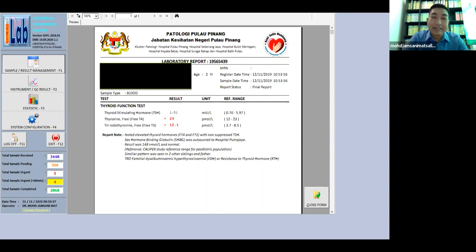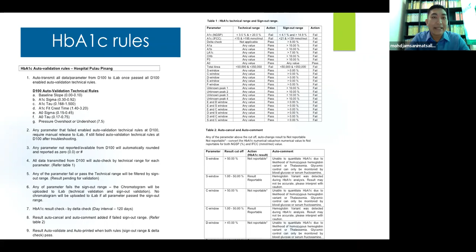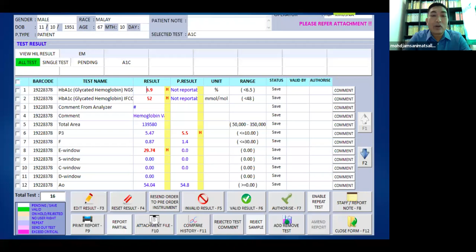For HbA1c, we have all the complex rules. We are using the HPLC method with the D100 analyzer, and we managed to do full auto validation based on the middleware from the analyzer as well as on the LIS, so that every single sample can be auto validated once it fulfills the chromatogram rules. The chromatogram is also automatically sent to us, and the duty chemical pathologists or the scientists can review any result based on the chromatogram in our laboratory information system. It tremendously reduces our workload and lab turnaround time, because most of the time we had to spend validating the chromatogram.